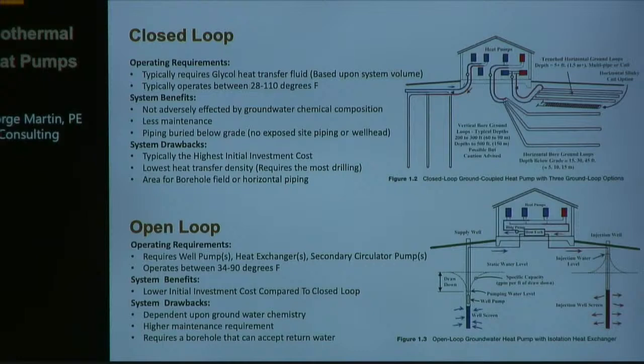Some pros for closed loop: no contact with groundwater, so no worry about that, and it's usually very low maintenance. The downside is it costs more because you need more boreholes for that exchange. Open loop pros are usually fewer wells, since it's based on the amount of water for your heat exchange, so you can have a cheaper system, but the cons are you have to worry about water management and you have to have water on site.